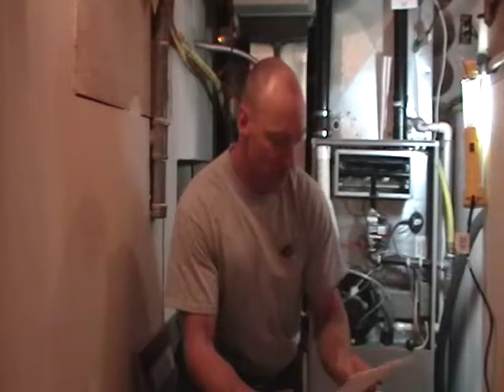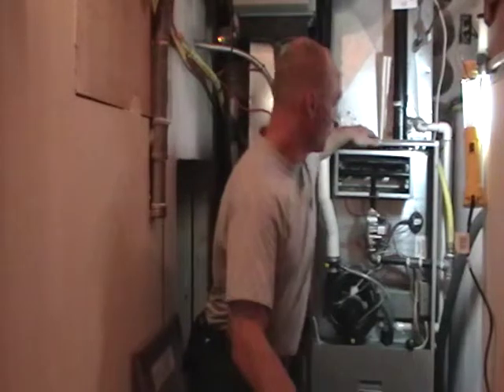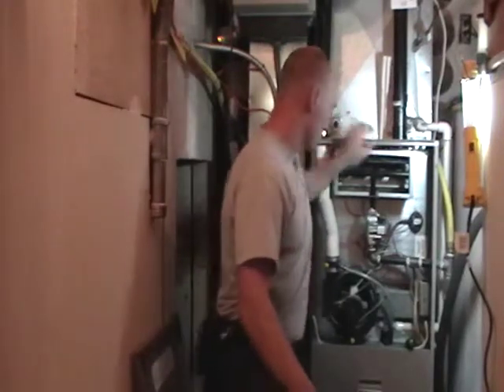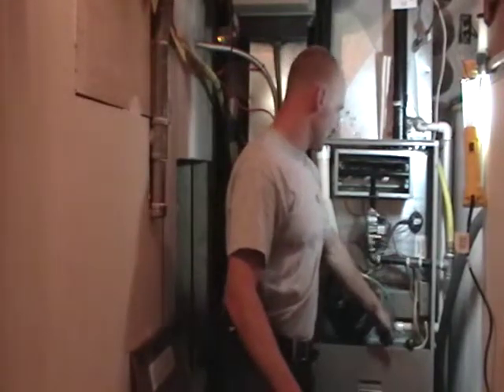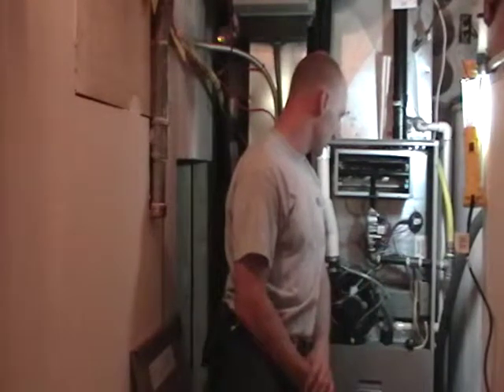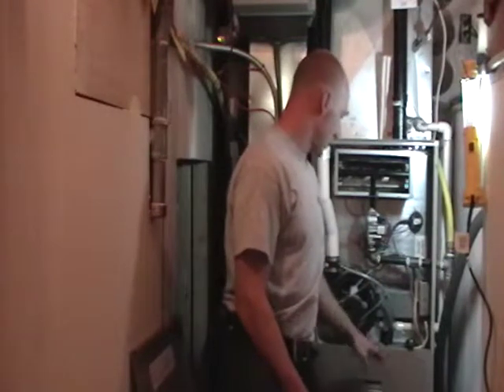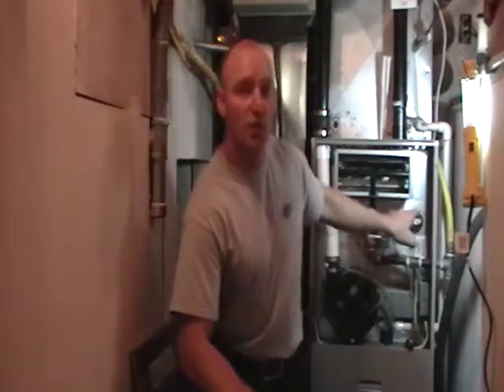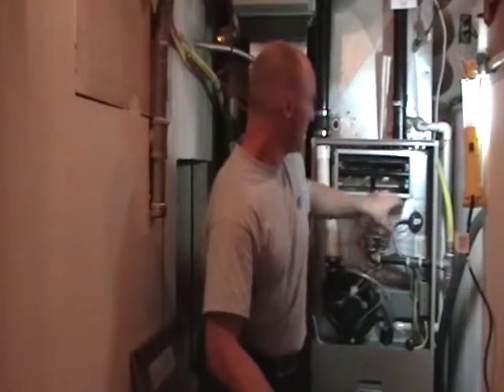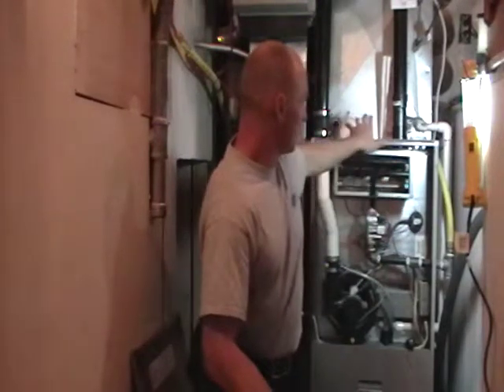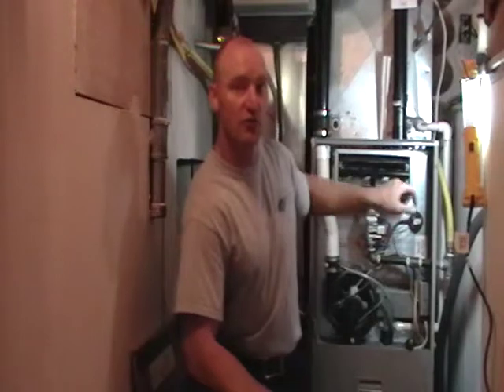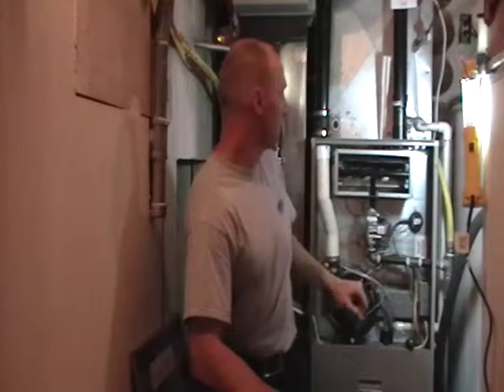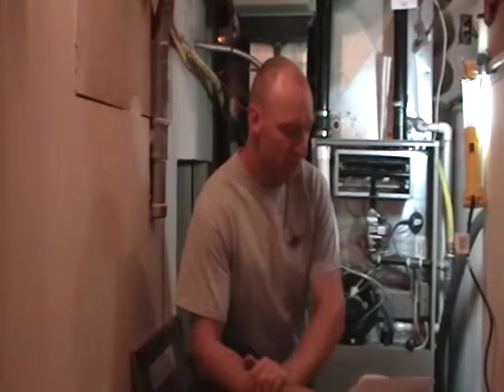Now, second, general cleanliness. Dirt is your enemy and cleanliness is next to godliness. So remember to keep your furnace clean. You can always use a shop vac to clean the top of the furnace. You can open up and clean the inside of the furnace as well as around the base. Now, this is especially true for a mid-efficient furnace where it draws combustion air from the space. With any dirt being around the furnace, if you're drawing that dirt through the combustion chamber, it can foul up the flame rod and the hot surface igniter. So you want to make sure you clean that off as well annually.